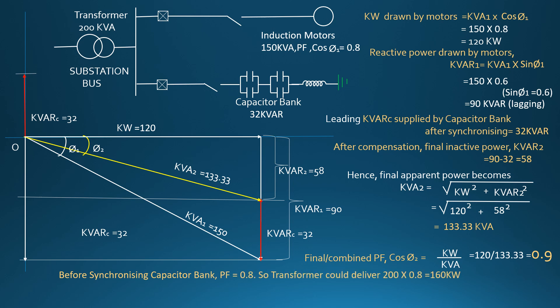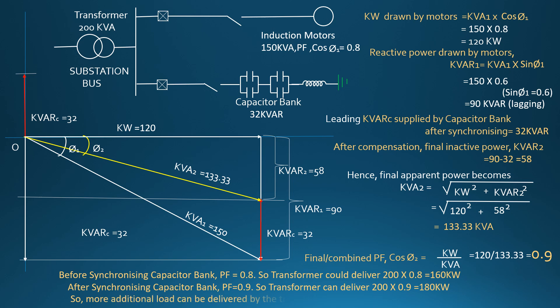Before connecting the capacitor bank, the power factor was 0.8 and the transformer could deliver 160 kW. But after connecting the capacitor bank, the power factor becomes 0.9 and the transformer can now deliver 180 kW. Therefore, the additional load that can be delivered by the transformer at 0.9 power factor equals 20 kW. So dear viewers, this was the explanation about power factor and the capacitor bank. Thank you.